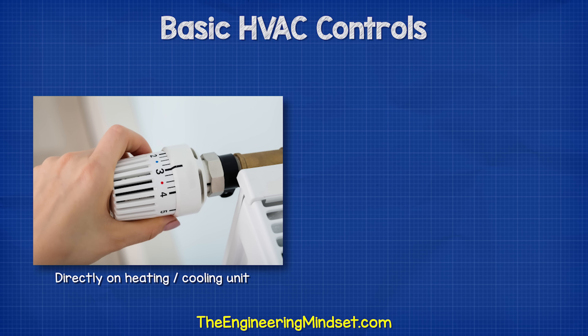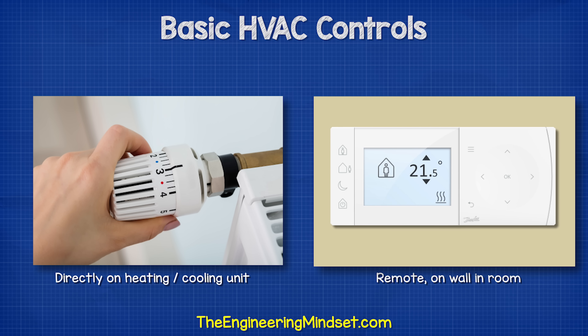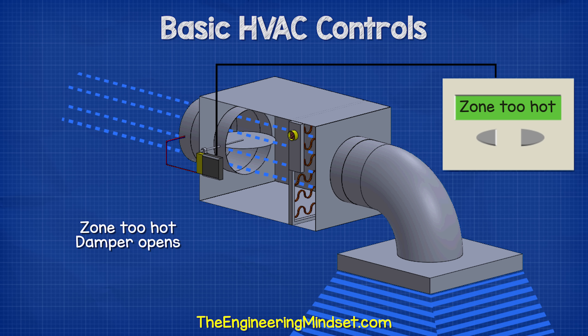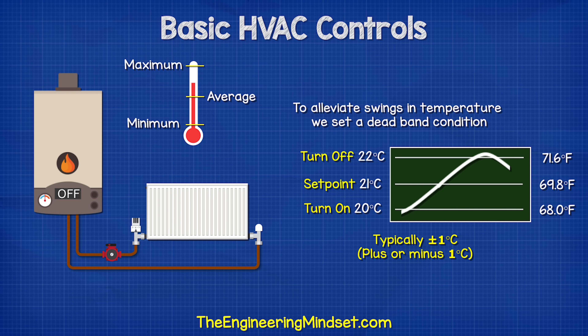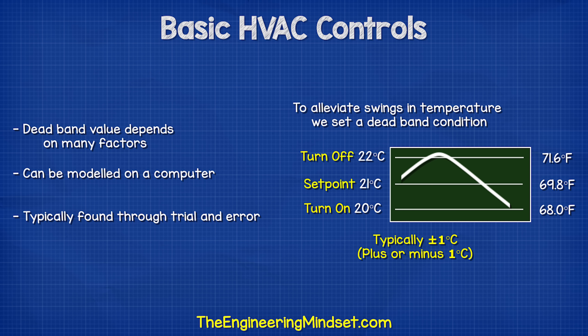The thermostat could be located on the output device, like a thermostatic radiator valve, or remotely, like a room thermostat which controls the position of a damper in a fan coil unit. To alleviate swings in temperature, we set a deadband condition, typically plus or minus 1 degree Celsius from the required temperature. For example, if we want a room temperature of 21 degrees Celsius with a deadband of plus or minus 1 degree, the heating will turn on when the room falls below 20 degrees Celsius and switch off when it is above 22 degrees Celsius, giving an average of 21 degrees. The deadband value is generally found through trial and error, with small incremental changes to find the optimal point where the room is comfortable and the system operates efficiently.